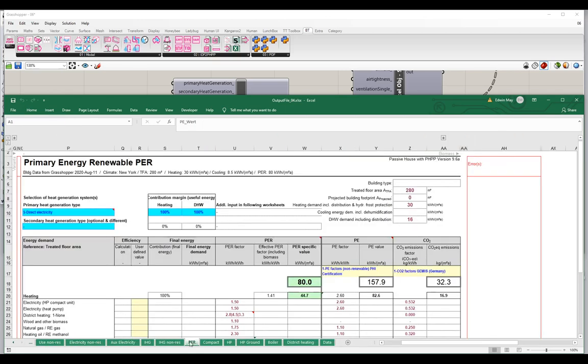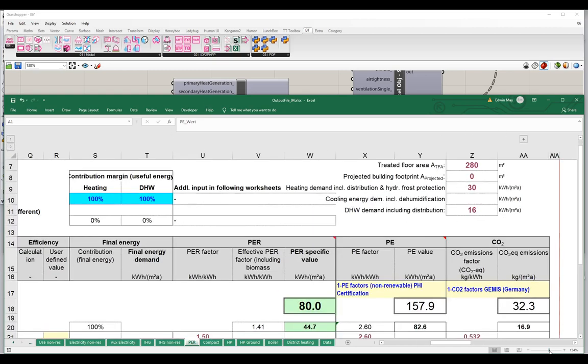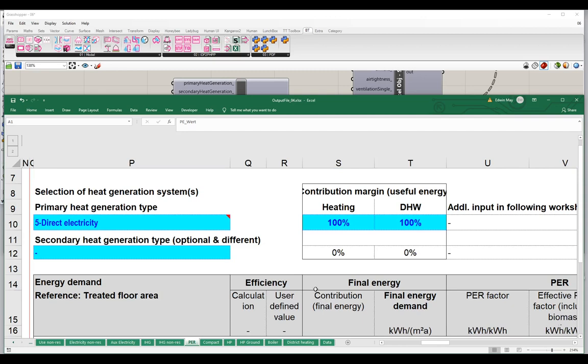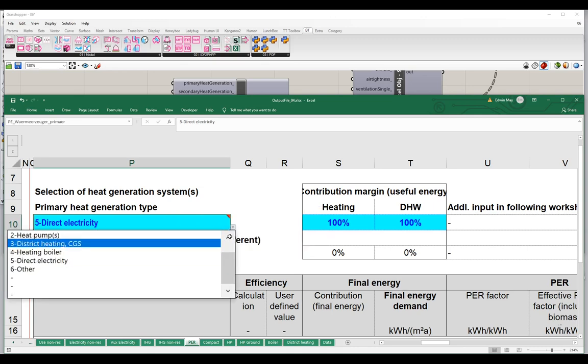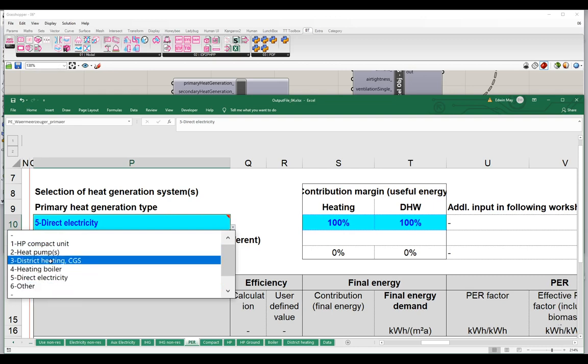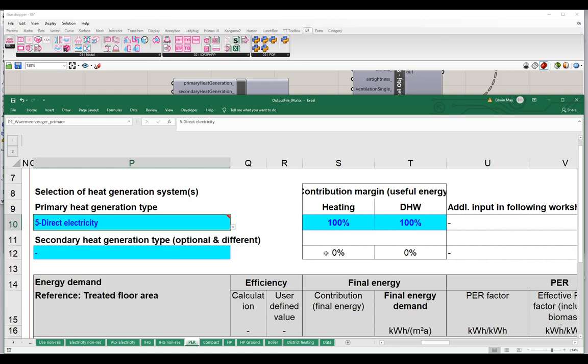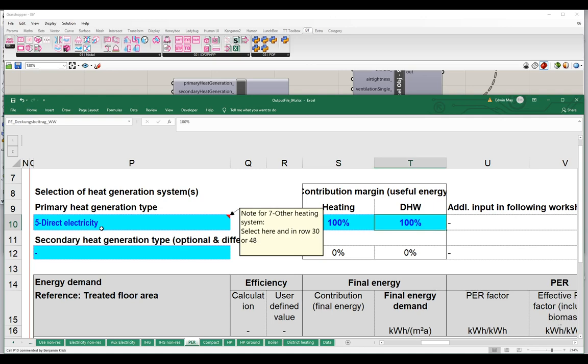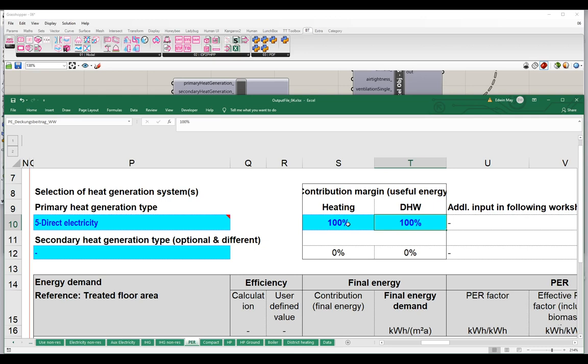Looking at the PER worksheet, at the top you can see what values are getting set. Our primary heat generator is direct electric. Other options include heat pumps, compact units, boilers, district heating, or user-determined. The way this table works: it asks what proportion — what percentage — of heating comes from the primary heat generator, and what percentage of domestic hot water comes from the primary generator. If we enter any number other than 100, the remainder comes from the secondary generator.